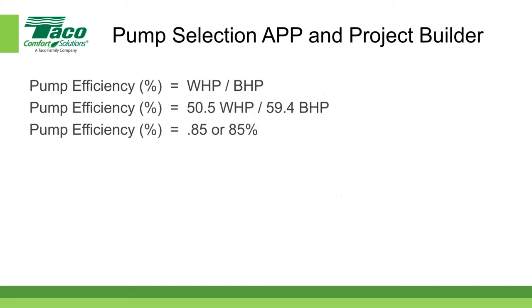Pump efficiency is equal to the water horsepower divided by the brake horsepower. In our case, the water horsepower was calculated at 50.5 and the brake horsepower was measured at 59.4. You divide 50.5 by 59.4 and you get 0.85, or 85%. So that's where pump efficiency comes from.